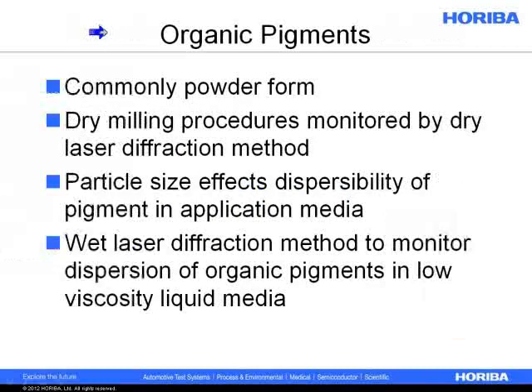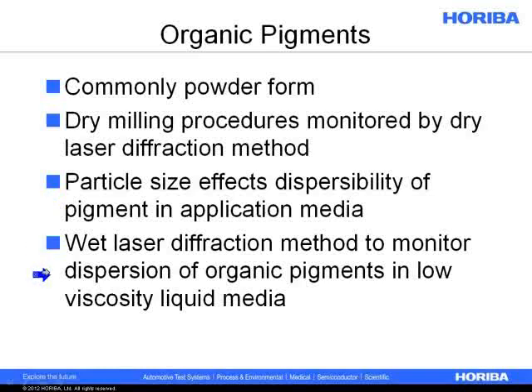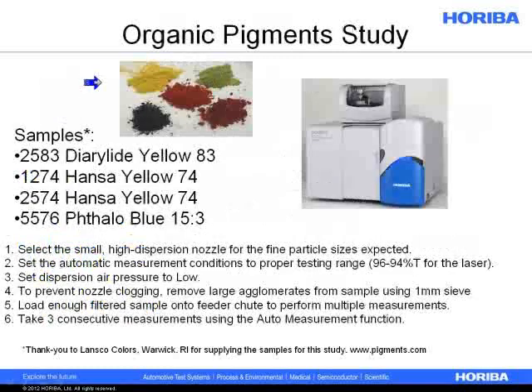We'll start with case studies for organic pigments, which are typically in powder form. We have many customers who use the LA-950 or LA-300. For dry monitoring it's always the LA-950. If you're doing dry milling and want to measure it as a dry powder, you can take the sample as you're milling it, bring it to the instrument, perform a quick measurement, and find out when you've reached the desired particle size distribution endpoint. For powders dispersed in liquid media, we might measure size or zeta potential. We'll show data from the LA-950 measuring both dry powders and samples dispersed in liquids.